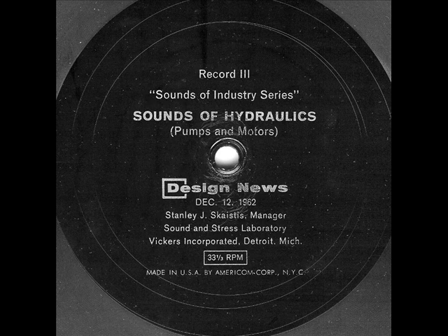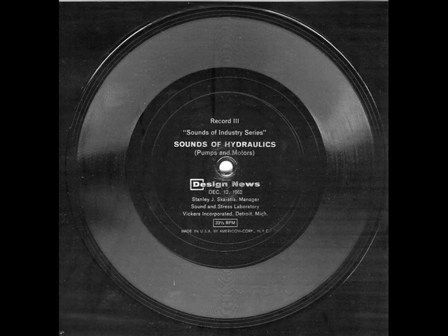In figure five, the relative effects of speed and pressure are compared for three combinations that have the same horsepower. Note that speed has a much greater effect than pressure: 900 RPM and 3000 PSI, 1800 RPM and 1500 PSI, and 3600 RPM and 750 PSI.